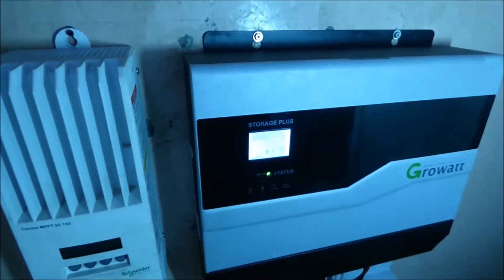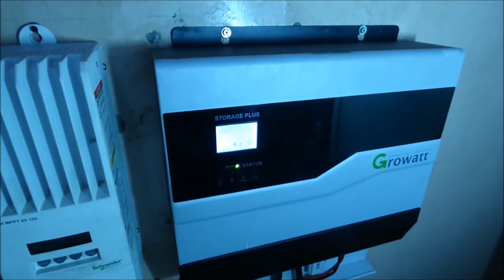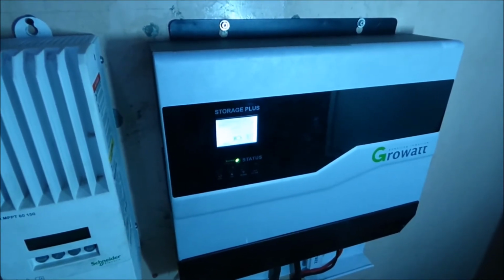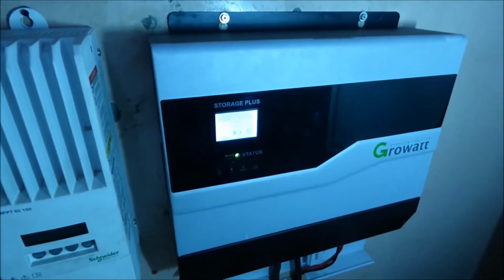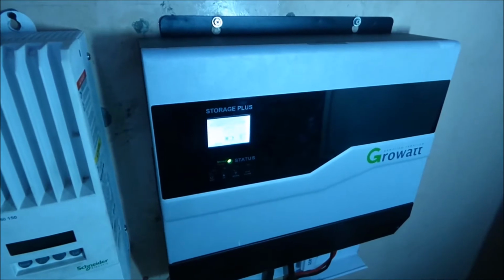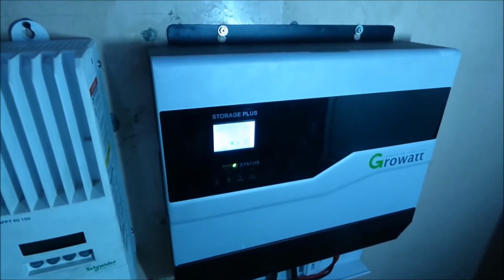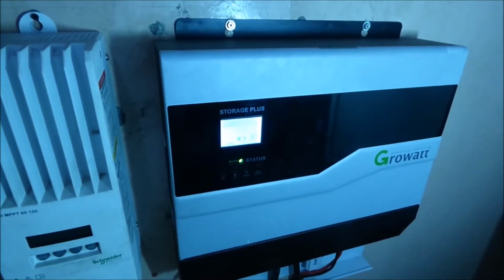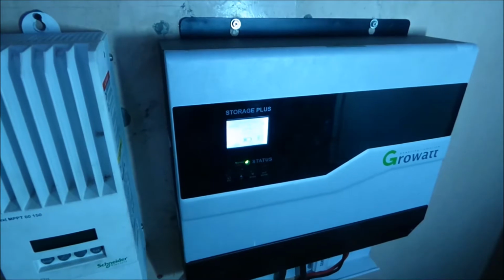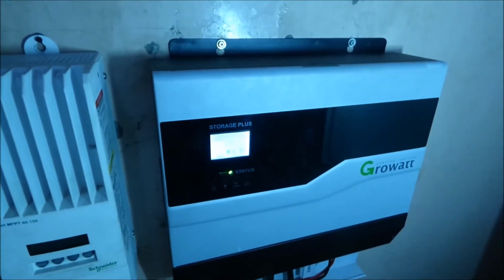We'd spent the last 2 weeks trying to update the firmware. Why was that important to us? Our float voltage was too low. They set the float voltage to 54 volts. We needed the float voltage at 56 volts. We also needed the bulk and absorption at 58 or 59 volts. It's set to 57.4. So we called the factory, they sent us updated firmware.